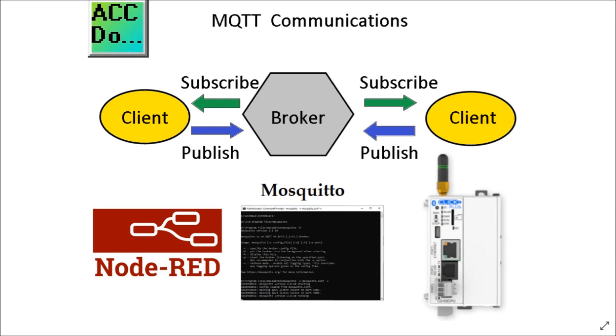This protocol is not for remote I/O or real-time deterministic applications. MQTT is a good solution for applications that move data from hundreds or thousands of machine sensors to clients in many networks. We will be installing a Windows-based broker called Mosquitto, and the Click Plus PLC will be one of the clients publishing and subscribing to the MQTT broker. Node-RED will be the other client publishing and subscribing to the broker, and each client will share the information.